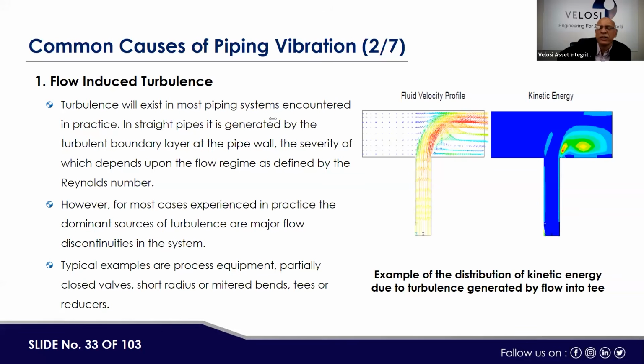Okay, here, first question, normal isolation valves, we normally consider them full bore valves. So these valves do not have any issue causing vibration, because we're talking about full bore valves. But if any valve is restricting the flow, like a control valve or pressure reduction valve or check valve, in those scenarios there could be a problem caused by noise, because if any component of the piping system is restricting or discontinuing the flow to a certain extent, that may have an effect. Like normally, we say that from one bend to another bend, a minimum length of so many pipe diameters should be provided, so that the flow is not restricted. Secondly, when elbows are there, we say that 5D, 3D, 1.5D should be there in the elbow, so that the flow is not all of a sudden changing direction and causing restriction.